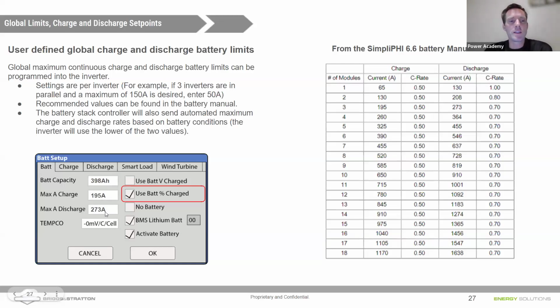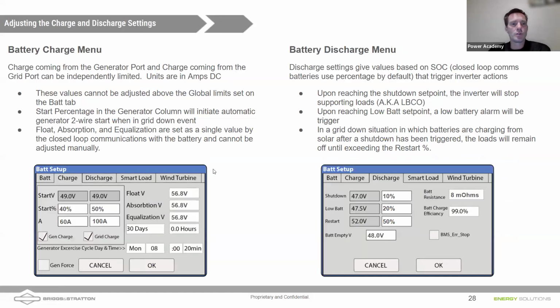On the discharge side of things, the inverter is only going to pull a maximum of 250 amps on discharge, but the battery bank, a 3-stack, can handle up to 273. The max setting you can use for a 15K there is 275. And this box should already be checked: use battery percentage, and that will allow you to make your settings based on the state of charge percentage of the battery. And you'll see that in the next set of slides here.